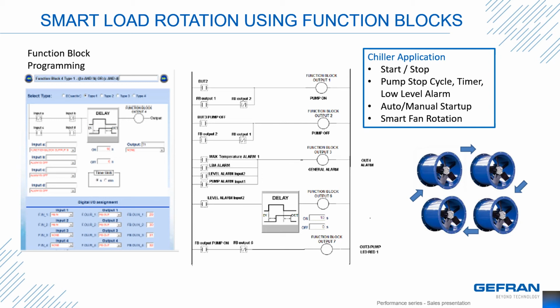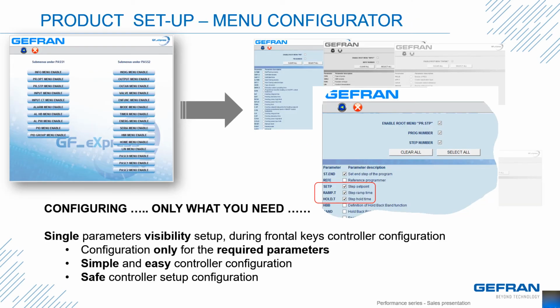And with the messages on the front of an 1850 or 1650, this could be a good HMI for the operator. You can control inside a standard menu what is available to the end user from the keypad. It makes it more secure and easier to use at the operator level, while you still have complete access via the Express tool. For example, on this page is the ramp soak. Maybe you would need the operator to change just a few items at the plant floor. In this example, I've selected step set point, step ramp time, step hold time, and the end step for creating the profile. Doing this limits the amount of detail the operator has to know and program.